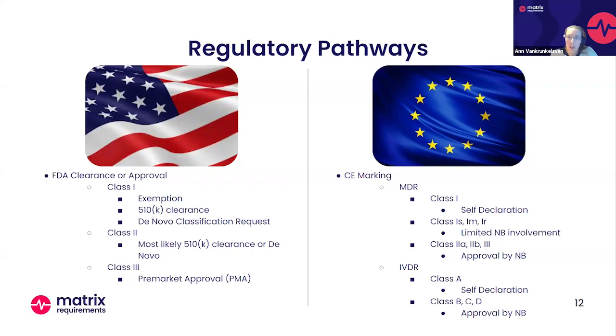When you want to bring a device to the European market, and it's a Class 1 that does not have a measuring function, is not a reusable surgical instrument, and is not sterile, you can bring this device to the market without obtaining a CE certificate first from a notified body. You will still have to submit your file to the competent authorities, which are the national authorities. Europe consists of 27 countries, so for each country you have to consider whether or not you have to submit that file, but you can already bring it to the market and you will get questions later on if there are any. As soon as there is a notified body involved, you need to obtain that CE certificate before you can bring the product to the market.